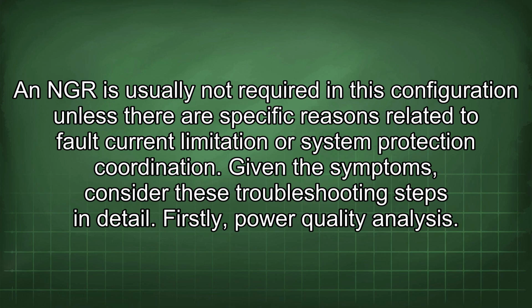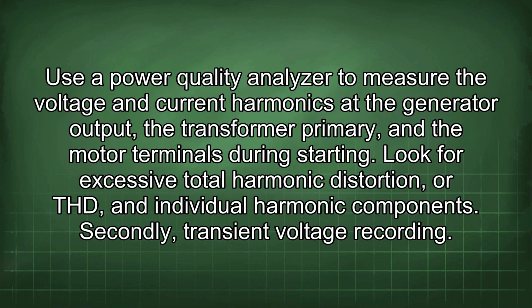Firstly, power quality analysis. Use a power quality analyzer to measure the voltage and current harmonics at the generator output, the transformer primary, and the motor terminals during starting. Look for excessive total harmonic distortion, or THD, and individual harmonic components.